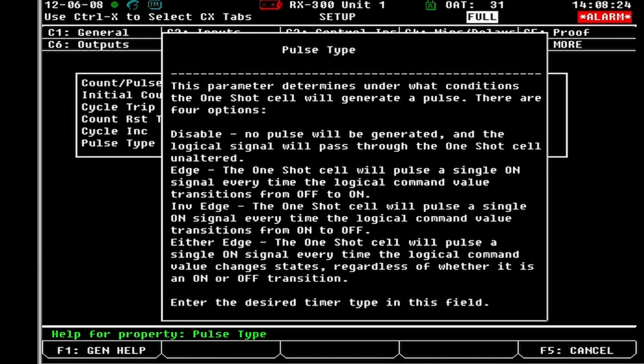So if you go to pulse type, this parameter determines under what conditions a one-shot cell will generate a pulse. There are 4 options: disable, no pulses; edge, the one-shot cell will pulse a single on signal every time the logic command value transitions from off to on; Inv edge, same thing as we talked about earlier. So this is for pulsing the output, if you wanted to use it as a pulse type output.